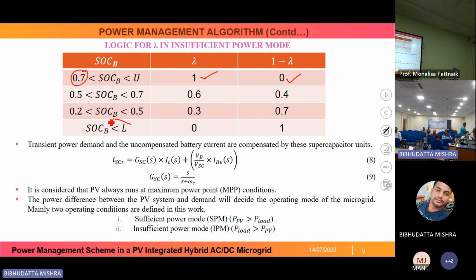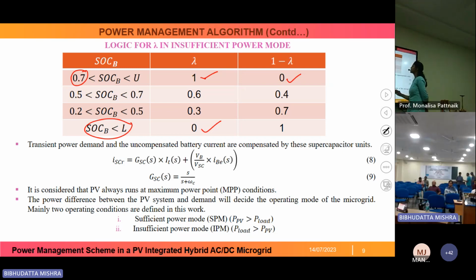Similarly, in the opposite case, when the battery SOC is less than its lower limit, that means the battery is completely discharged. At that time, lambda is set to 0. That means the battery will not supply any power to the system and the grid will supply the total average power requirement to the system. So in this way, we can share the average power between the grid and the battery units. Then we come to the supercapacitor units.